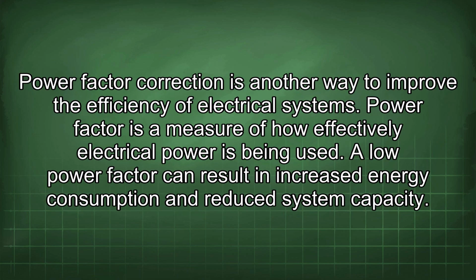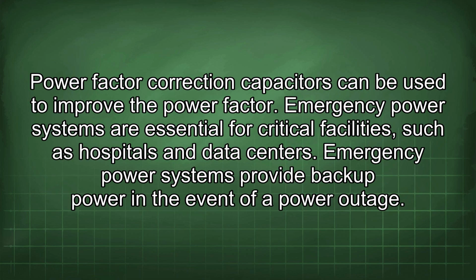Power factor correction is another way to improve the efficiency of electrical systems. Power factor is a measure of how effectively electrical power is being used. A low power factor can result in increased energy consumption and reduced system capacity. Power factor correction capacitors can be used to improve the power factor.